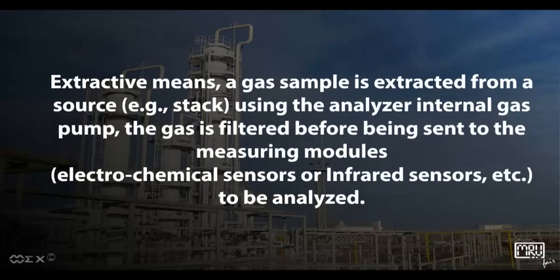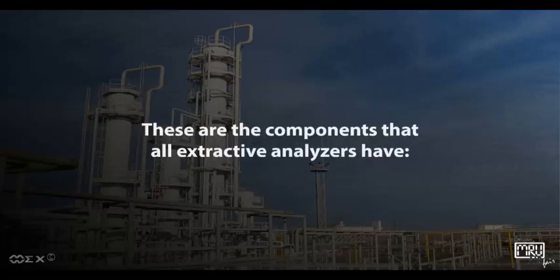Extractive means a gas sample is extracted from a source — for example, a stack — using the analyzer's internal gas pump. The gas is filtered before being sent to the measuring modules: electrochemical sensors, infrared sensors, etc., to be analyzed.